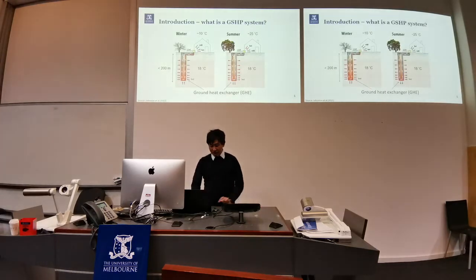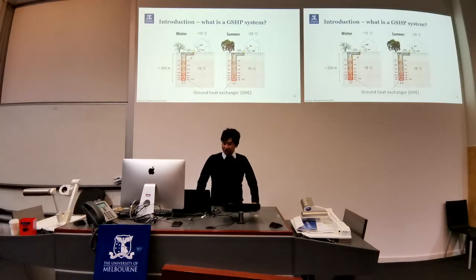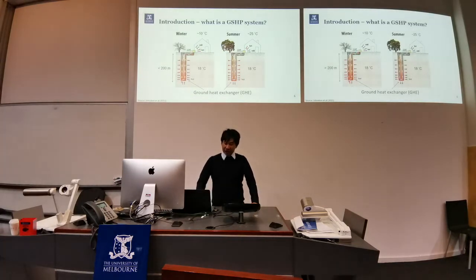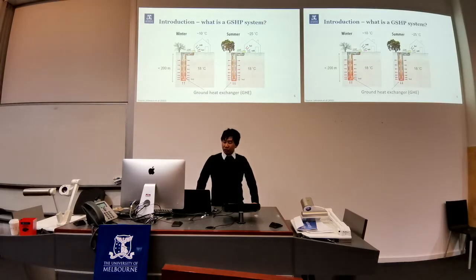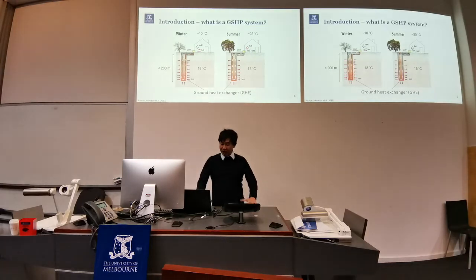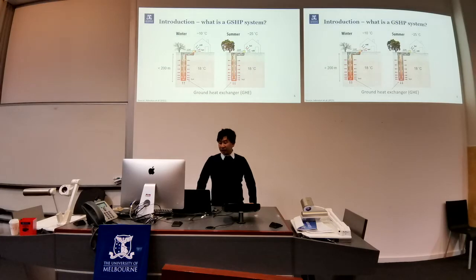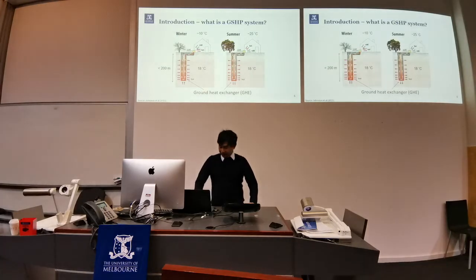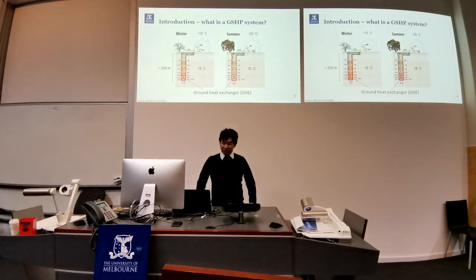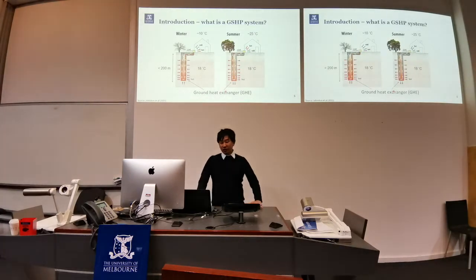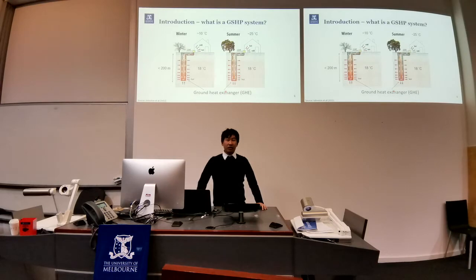One technology that might help us is by using ground source heat pump system. So in winter, we have water circulated inside this ground heat exchanger. The water will pick up heat from the ground, and by using the heat pump, this will be upgraded to provide heat to the building. In summer, the reverse happens, where heat from the building is moved into the ground. This technology is more efficient than typical air conditioning.